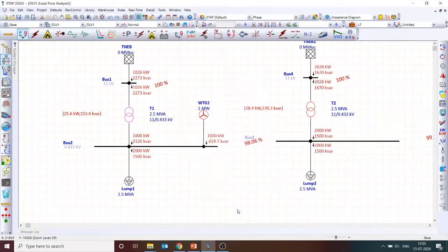So now let me go back to this answer. Let's look at the difference. When the 2000 kilowatt is my demand, I am generating 1000 kilowatt from the wind turbine generator. Again, please remember, power system is the most dynamic system in the world. Load flow analysis is a steady state analysis. So you are not doing a dynamic analysis. You are trying to capture only one operating point of the varying power system dynamics, right?